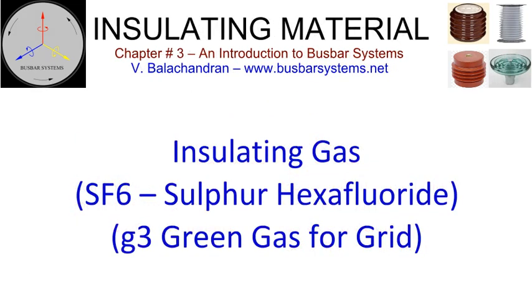Insulating gas SF6 and G3. With the increase in the transmission voltage, there arose a need to make the associated switchgear equipment compact, free from environmental constraints. Man-made sulfur hexafluoride gas with excellent dielectric properties had been synthesized in the early part of the last century and used initially in medium and high voltage circuit breakers and subsequently in gas-insulated switchgear followed by gas-insulated transmission lines.